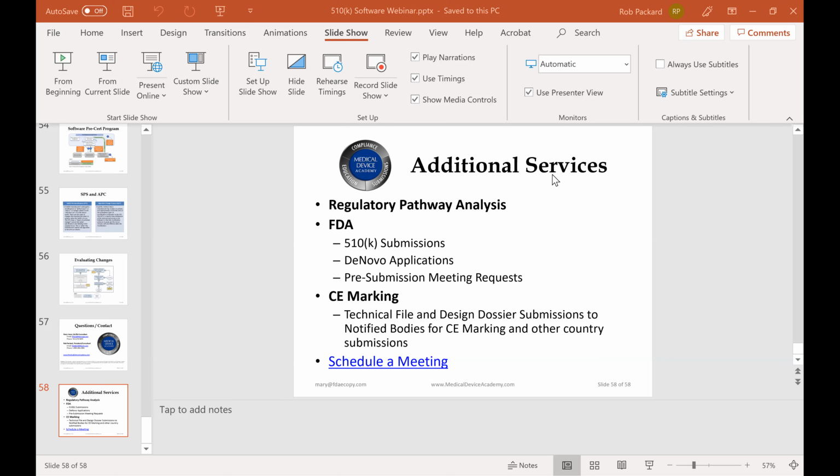But other modifications, they've really been trying to increase the number of specials that they review and to allow more things to go through that. But if it's a catch-up 510K and your product's already on the market, I would encourage you to take the traditional route. And here's my rationale. It doesn't cost any difference one way or another. You're not on any timeline that's urgent here because you already have the product on the market. You're just trying to get the FDA's documentation current. And therefore, 30 days versus 90 days, what do you care? You're already on the market. Otherwise, it's not a catch-up.